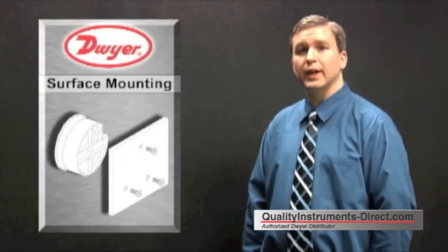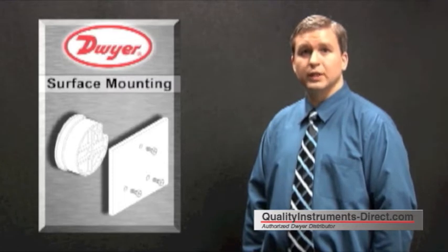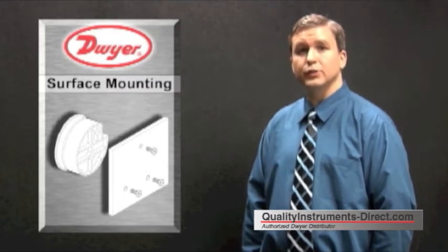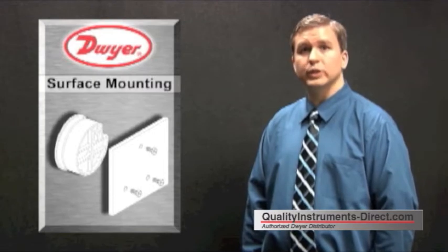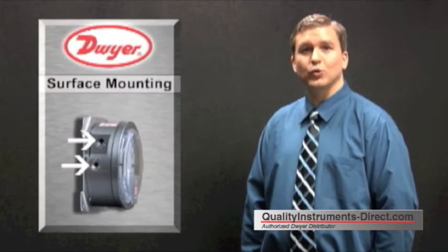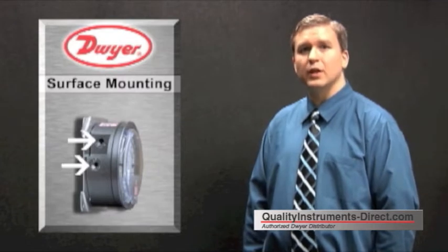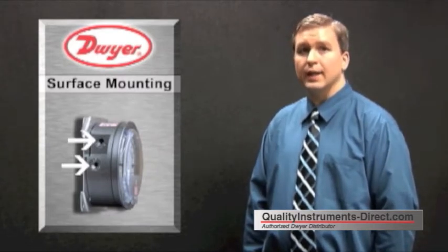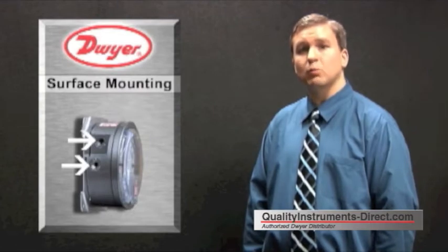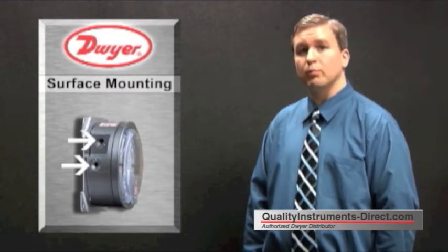If you wish to simply mount the gauge directly to a surface, use three 6-32 machine screws of appropriate length to reach through the thickness of the surface. Of course, using the surface methods, the process tubing must be connected to the side of the gauge and not through the back connections unless proper holes are drilled through the bracket and wall.